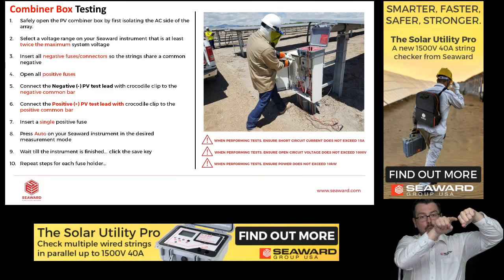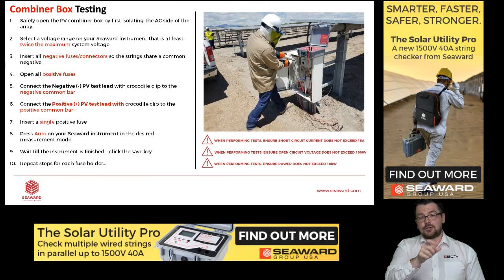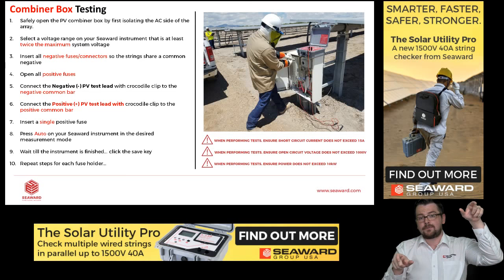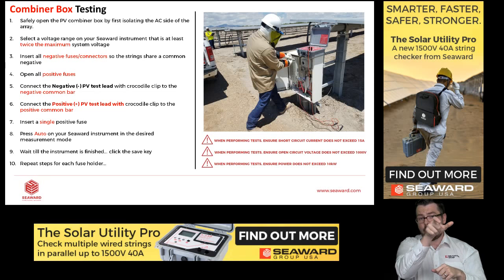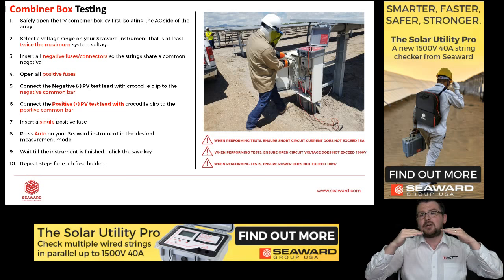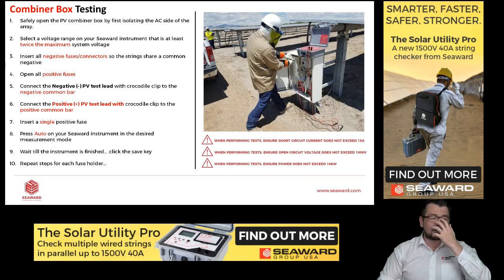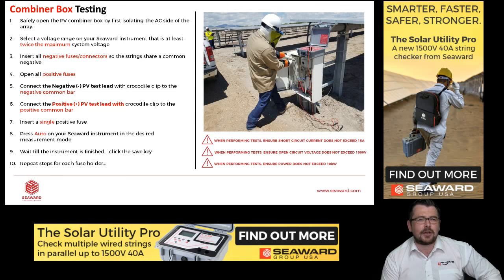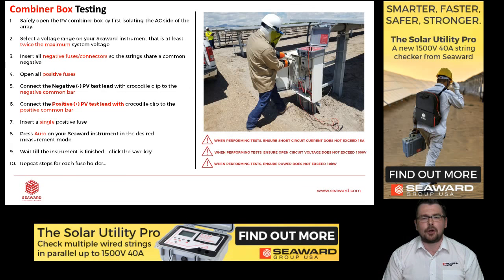Now what we do is we insert one fuse, we push test. So that means we're testing one single string in that combiner box. We run the test, we save it, open the fuse, close the next fuse, test, save it, open the fuse, close the next fuse, test, save it. And this way we can quickly go down the combiner box and run through the whole combiner box. I think we maybe did a 30-string combiner box in about 13 to 15 minutes with a PV210, and similarly with a Solar Utility Pro. The PV analyzer from Solmetric is very quick also, giving us a good IV curve sweep. So that's a very quick method to be able to test in a PV combiner box.